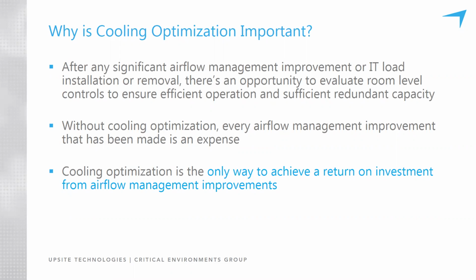You look at that second bullet there, right? Without doing any of these steps after the containment, every airflow management improvement that's been made is just an expense. So a few examples that I'd like to share might be raising the set points of your CRAC or CRAH units to more effectively produce the cold air required. That equals energy savings. And quite honestly, doing any of these changes post-containment, for whatever the reason you're going about it, the energy savings usually does come along for the ride. But this could be a key step in what you do as an owner once the containment's implemented.